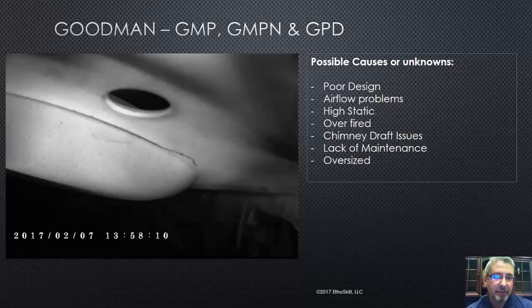So possible causes: we could have some airflow problems here. Clearly there were some significant problems. We could have an inferior product, maybe inferior metal, or an inferior process in building that heat exchanger. We could have something that was overfired, too high gas pressure. We could have chimney draft issues, lack of maintenance. That furnace could be oversized. So it's all the things we teach in Rapidtech -- you have to know what to look for. Here's my concern. This is the biggest concern I have as an HVAC trainer and owner.